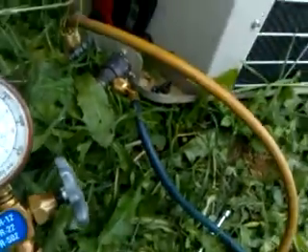If we're condensing at 115 here, some of the time, even if we call it 112, which is where it dives to, I only got 82 degrees on the liquid line. Suction line is reading... Oh, can we see it? 75 and a half, 75.3.